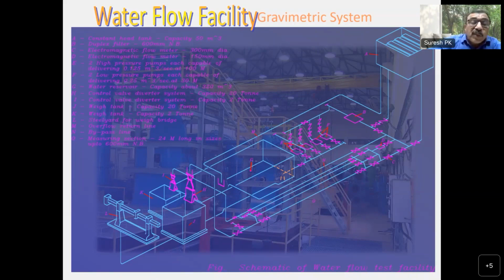So then the mass part, if you cover, then you have the density. Density you measure using densitometers. The densitometer is calibrated against another density system. So that density system is calibrated against the standard density fluids. The standard density fluids are supplied by some other organizations which calibrate against international standards. So the density is three steps away from the international standard. Therefore you have the uncertainty of all these three steps.